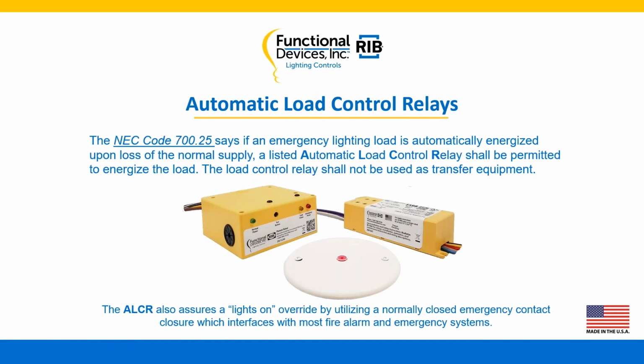Next, we'd like to talk about automatic load control relays. The NEC code 700.25 says if an emergency lighting load is automatically energized upon a loss of normal supply, a listed automatic load control relay, that's ALCR, shall be permitted to energize the load. Mainly, one focus here is they do not want this to be used as a transfer device or a piece of transfer equipment. And really what ends up happening is you have the utilization of lights on override with a fire alarm or emergency system.